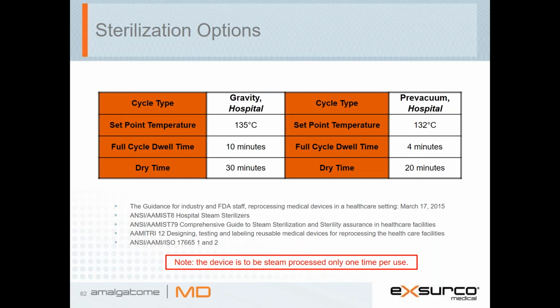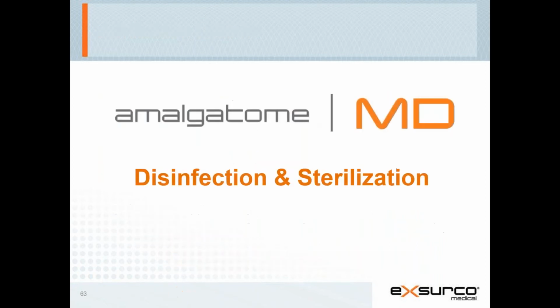Gravity air displacement steam sterilization. Set temperature to 135 degrees Celsius for a full cycle dwell time of 10 minutes with a dry time of 30 minutes. Pre-vacuum steam sterilization. Set temperature to 132 degrees Celsius for a full cycle dwell time of 4 minutes with a dry time of 20 minutes. Please note, it is to be processed one time only per use.